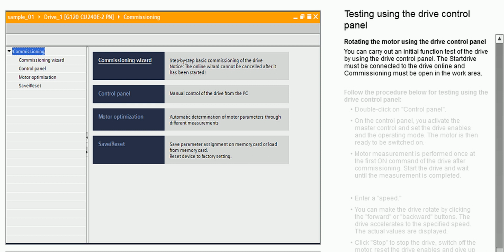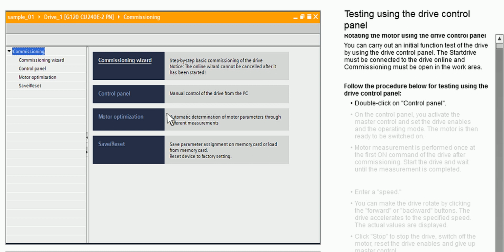Rotating the motor using the drive control panel. By means of the drive control panel, you can carry out an initial function test of the drive. Startdrive must be connected to the drive online and commissioning must be open in the work area. Follow the procedure below for testing using the drive control panel.